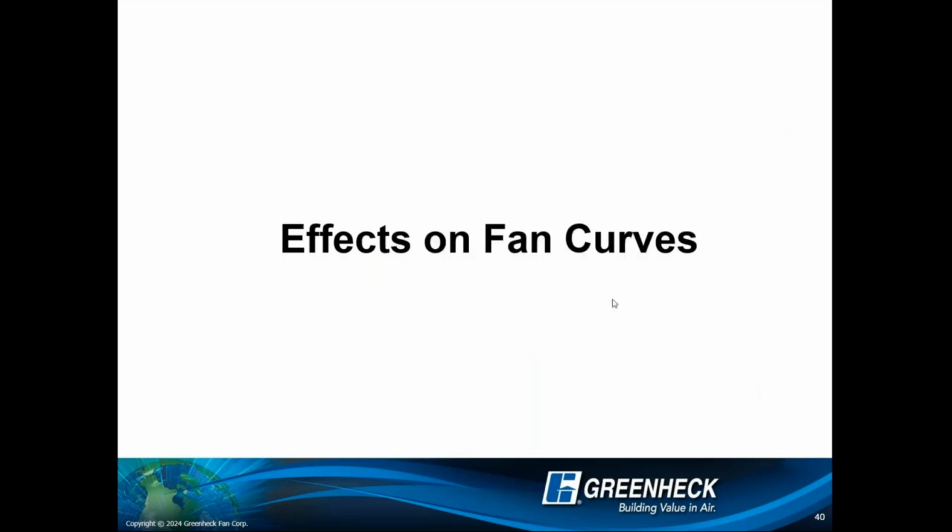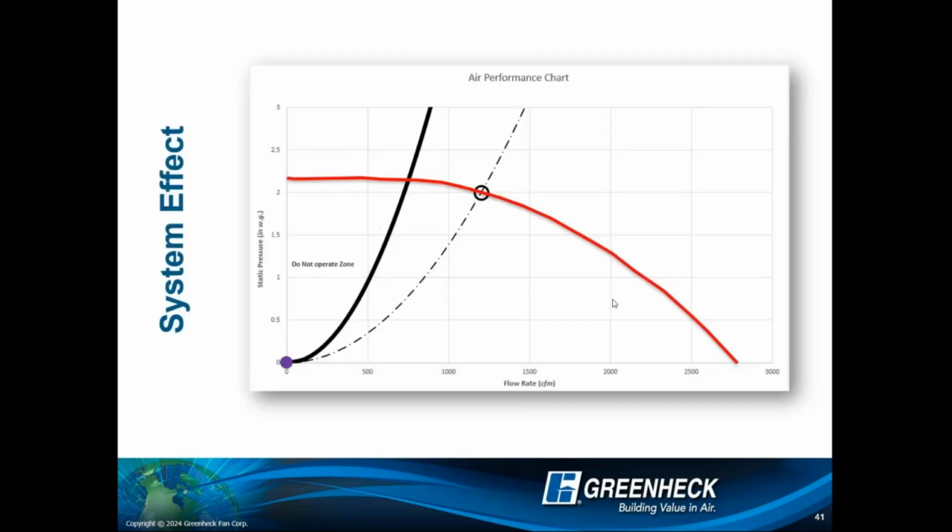All right, I'm gonna jump back to fan curves. I just can't get enough of these, but I want to relate it to something that we even brought up in the beginning. How can I affect the fan curve? All right, so here we have our fan curve, 1200 at 2 inches, right? This is all that beautiful data that I collected as a manufacturer.